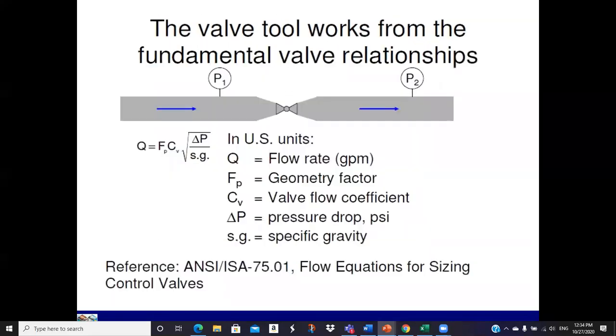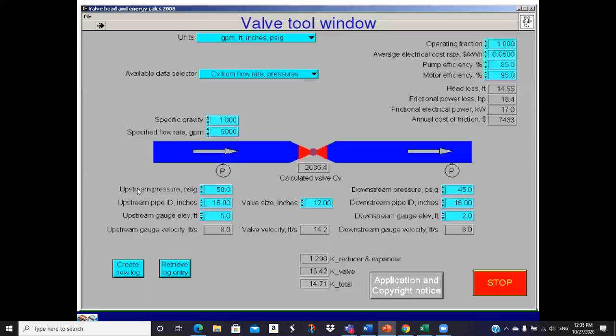This is not the screen yet, but we'll see the actual valve tool screen here in a second. This is some fundamentals. So the valve tool uses this valve equation, and notice here the F sub P is included, and the F sub P is programmed into the valve tool. So it's a very handy way to include any changes in diameter into the analysis. It automatically occurs when you put the inputs into the program. CV, valve flow coefficient, pressure drop, we've got an upstream and a downstream pressure, and specific gravity. So pretty straightforward. Nice little tool. Okay, so there's what the valve tool looks like.